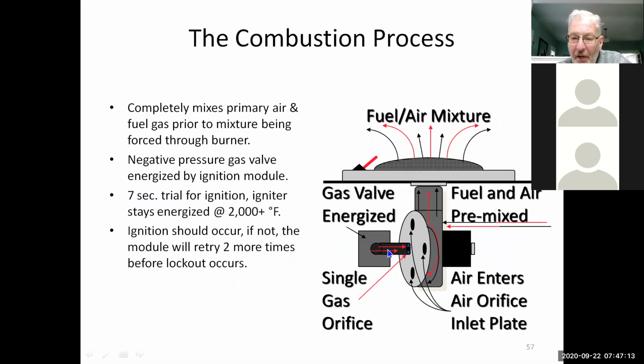Okay, so what it does is it takes the gas air and mixes it in the combustion motor here, delivers it to this convex stainless steel screen. The igniter is right here. The igniter lights off the gas air mixture, and the igniter also becomes our flame sensor. So it mixes it in the inducer. It's a negative pressure system. You have a 7-second trial for ignition, and you have 2 retries. What's going to happen is you get a 7-second trial for ignition. There's a 45-second warm-up on the igniter. So after that 45 seconds, it's your 7-second trial for ignition.